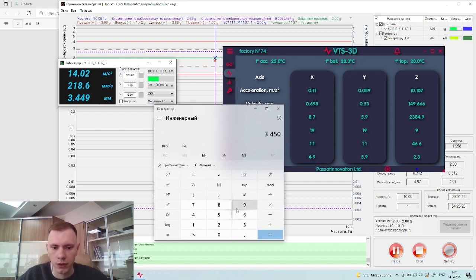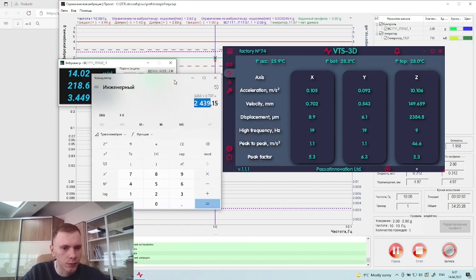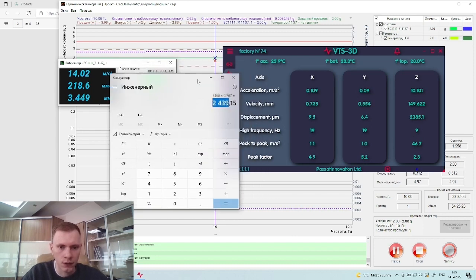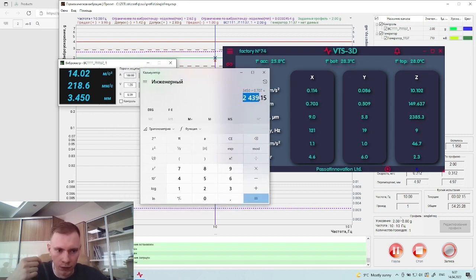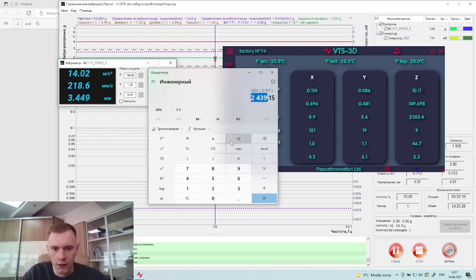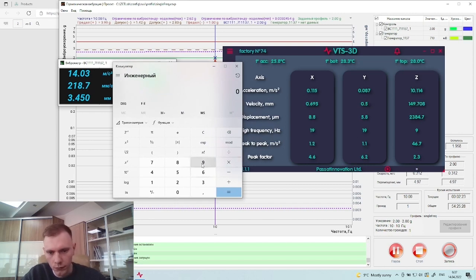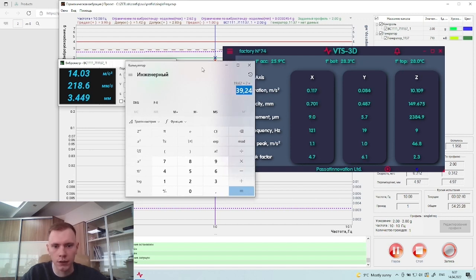And the last one is displacement. Almost the same. You can calculate the error percentage by yourself. And as you can see, our sensor says that the frequency with the highest energy is 9 Hertz. We have 10 on our vibration exciter. Let's also see the peak to peak. Peak to peak is a magnitude characteristic, so we need to calculate our 2G and then multiply it by 2. Okay, 39.24. A little error we have here.